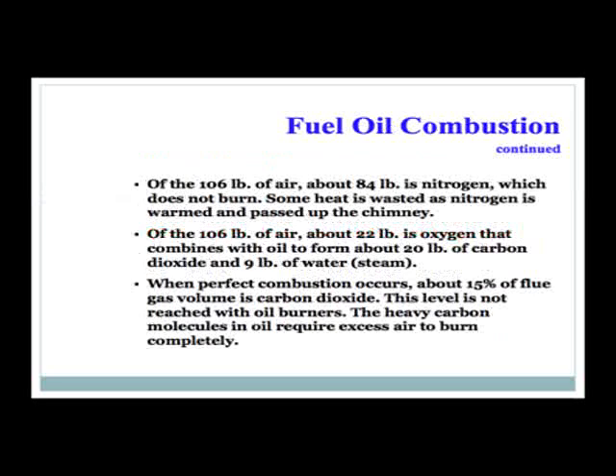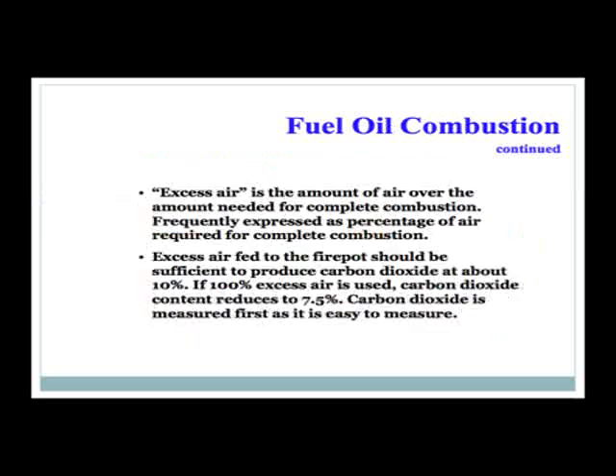When perfect combustion occurs, about 15% of the gas volume is carbon dioxide, but this level is not reached with oil burners. The heavy carbon molecules in the oil require excess air to burn completely. Excess air is the amount of air over what is needed for complete combustion, frequently expressed as a percentage. Excess air fed into the combustion chamber should produce carbon dioxide at about 10%. If 100% excess air is used, carbon dioxide content reduces to 7.5%. Carbon dioxide is measured first as it is the easiest to measure.